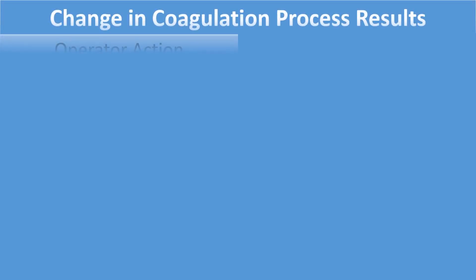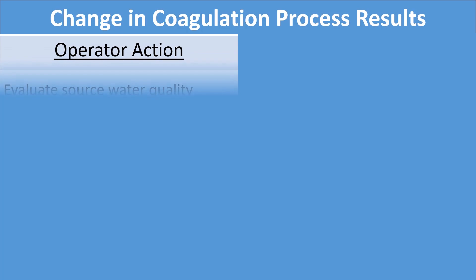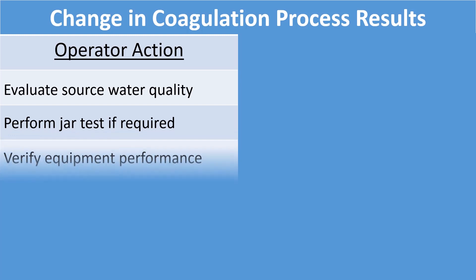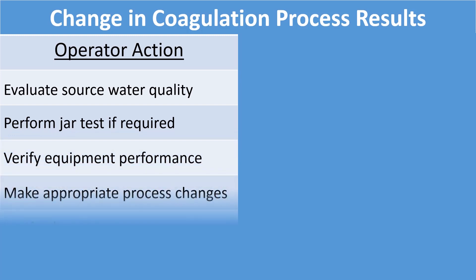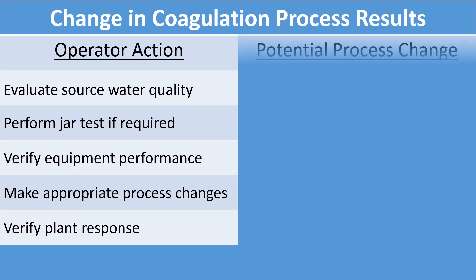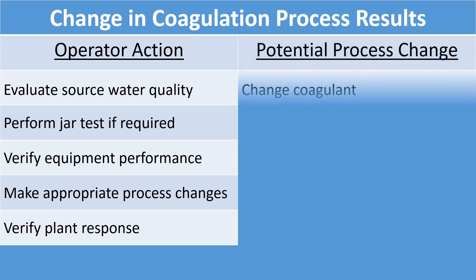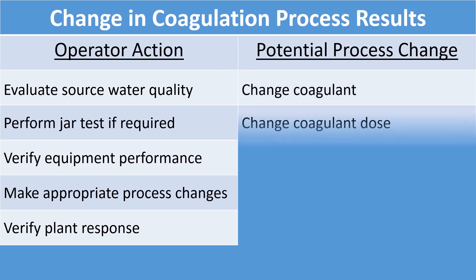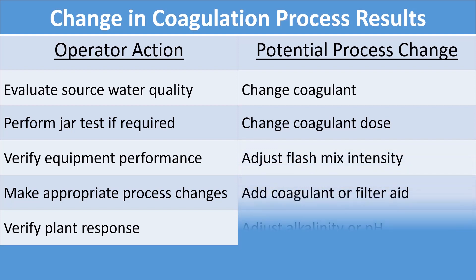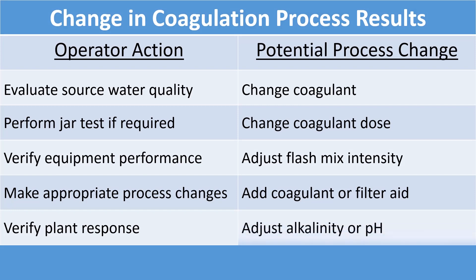If there is a change in coagulation process results, similar operator actions are required. You evaluate the source water quality, perform a jar test if required, verify that equipment is performing properly, and make any changes as appropriate. Then verify plant response after any change is made. Potential process changes include changing the coagulant, adjusting your dose, adjusting flash mix intensity, adding a coagulant or filter aid, or adjusting the alkalinity or pH. These actions are very similar in both circumstances.